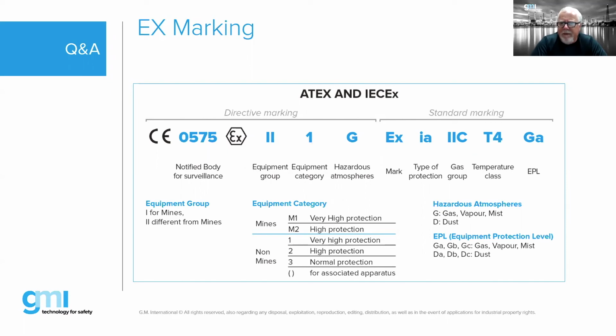So what that T4 is telling us, just hypothetically, if we didn't see any ambient marked on this product, let's just assume at +40 degrees C, a T4 marking is telling us that the relevant surface of that barrier will never exceed 135 degrees C under a fault condition. Okay. If it was marked T5, that would mean that product would never exceed 100 degrees C. If it was marked T6, it would never exceed 85 degrees C.